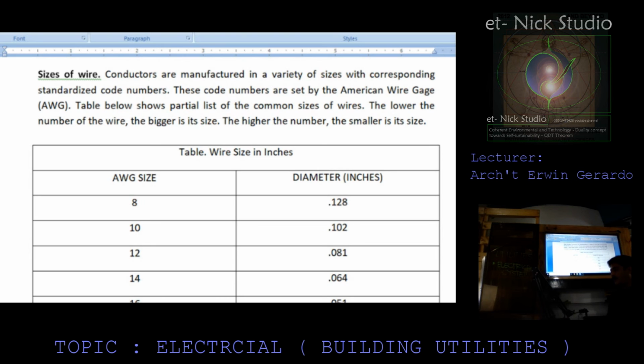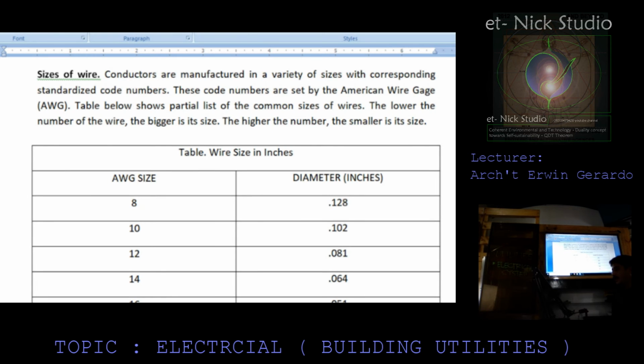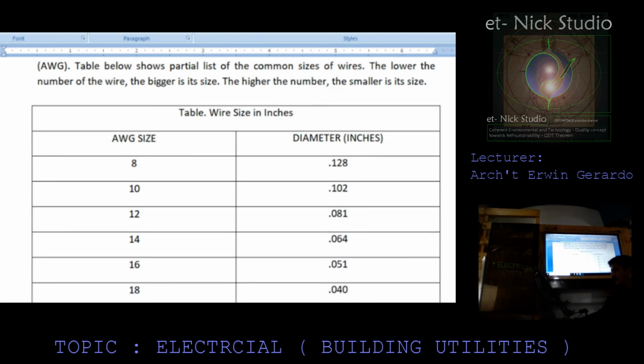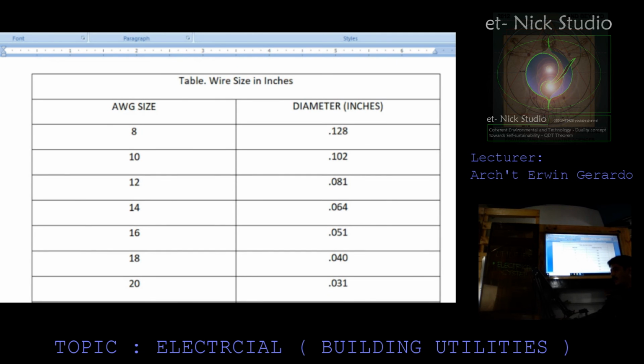Sizes of wires. Conductors are manufactured in a variety of sizes with corresponding standardized code numbers. These code numbers are set by the American Wire Gauge, abbreviated as AWG. The table below shows a partial list of the common sizes of wires. The lower the number of the wire, the bigger its size. The higher the number, the smaller its size.